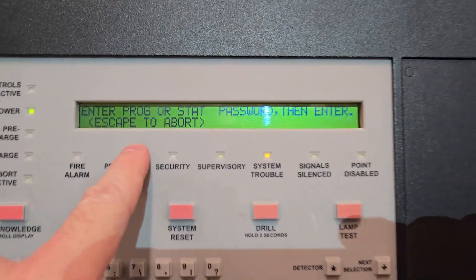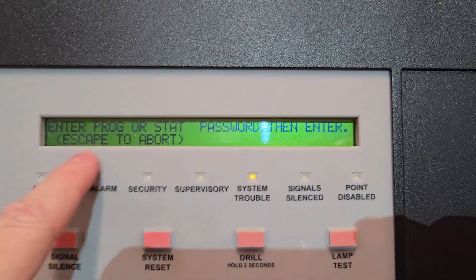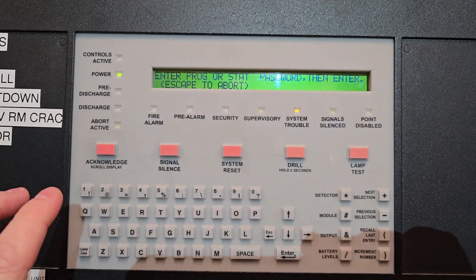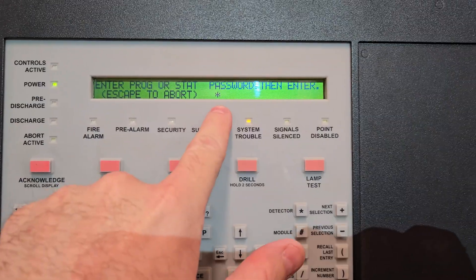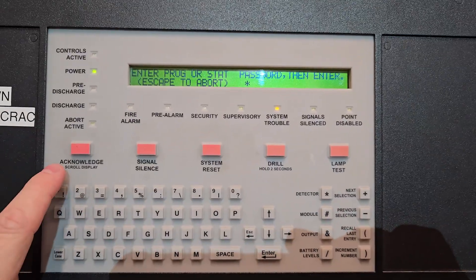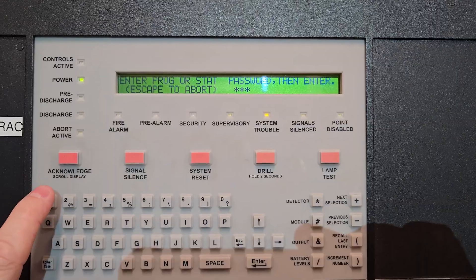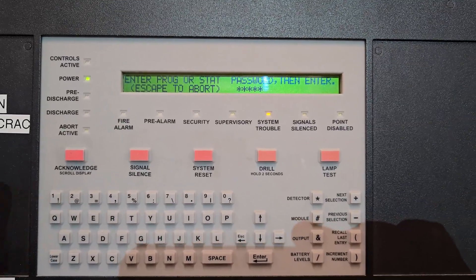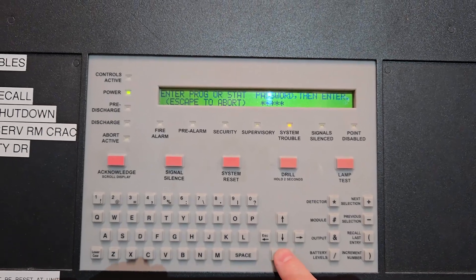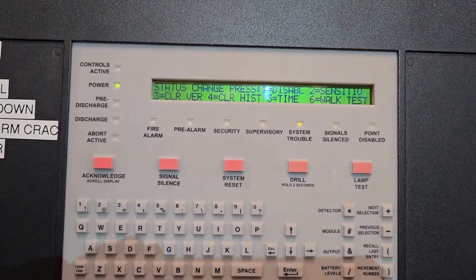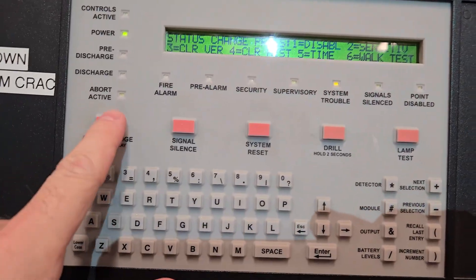Now it's going to say 'enter programming password.' The password is five ones, so I'm going to hit the one five times. You can see the little stars come up as I hit it: one, two, three, four, five. Now I hit Enter and we're in the menu. The trouble activates when you're in the menu, so I'm just going to acknowledge and silence the beep.